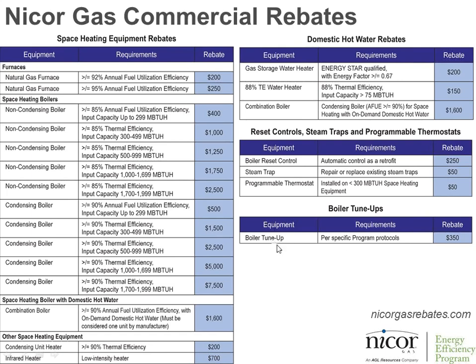One very popular rebate is the boiler tune-up program, where you can get $350 for tuning up your boiler. The contractor has to go through a checklist of items to make sure it's operating correctly and clean the heat exchangers, then perform a combustion analysis test to prove out its efficiency, print off that analysis, and turn it in with their report for the up to $350 rebate. For very small boilers, $350 is an awesome rebate that pretty much pays for the whole tune-up.